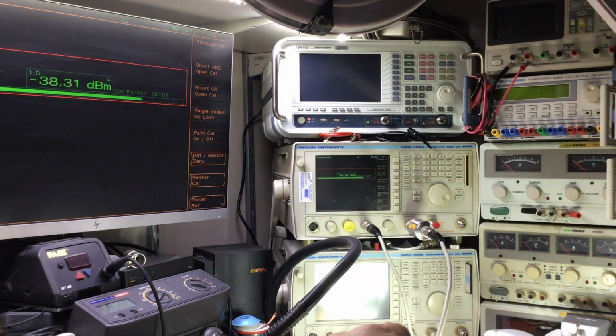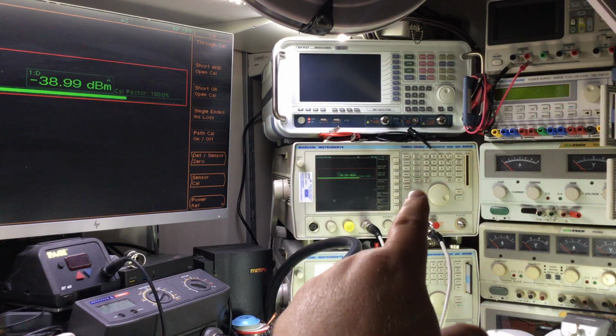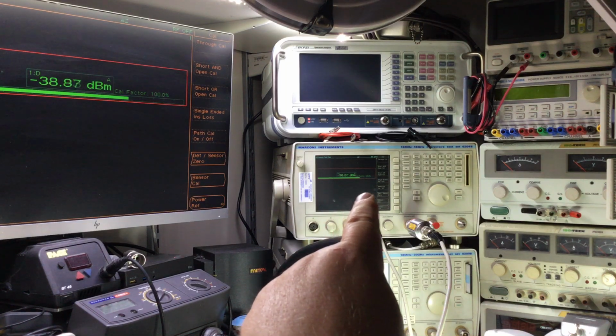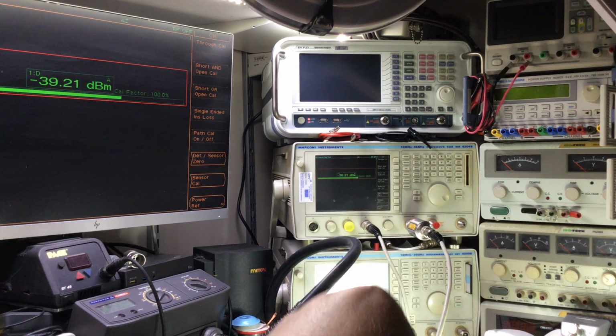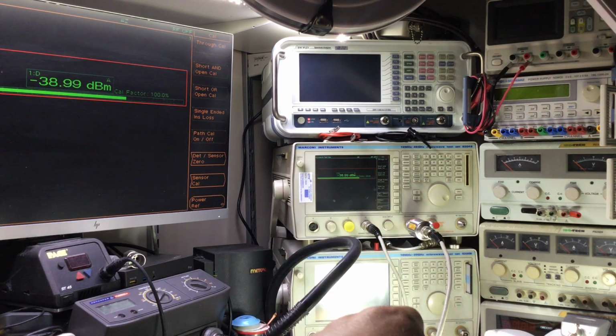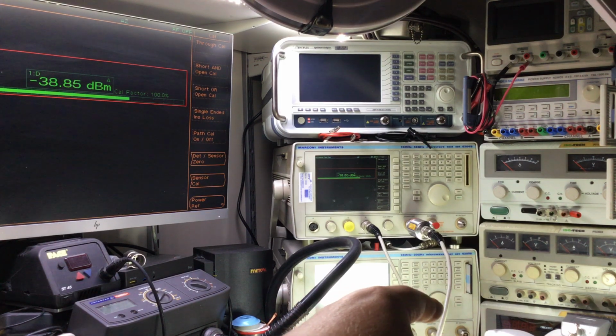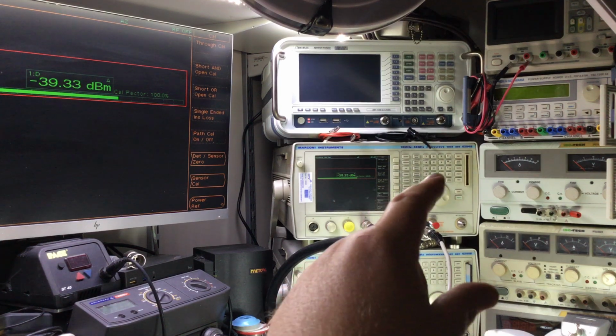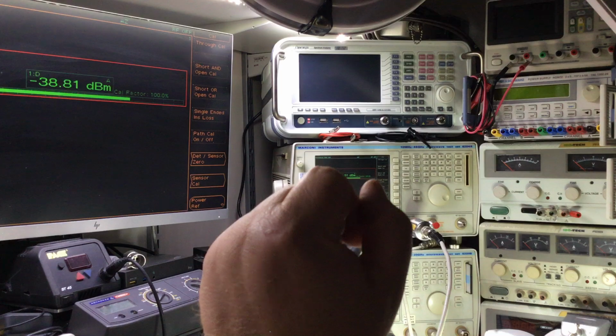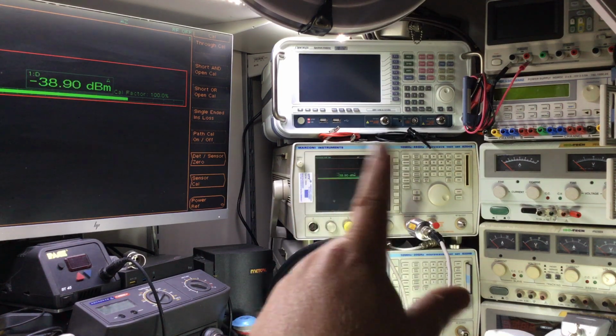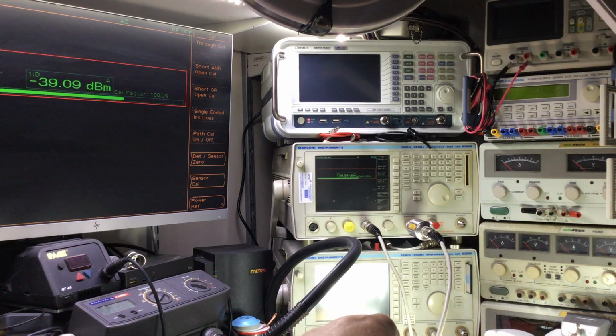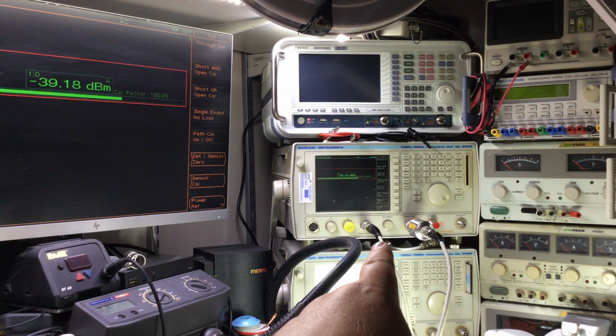This particular microwave test set we're going to use for two things. We're going to use the microwave test set with the power sensor here to verify the HP meter that we're testing has a 0 dBm output from its calibrated reference port. Otherwise, if the output of the meter isn't correct, then its sensor won't be calibrated correctly against it, so all its measurements will be out. So that's test number 1 we're going to be able to do using this sensor. But test number 2 is this particular microwave test set has a frequency range up to 46 gigahertz.